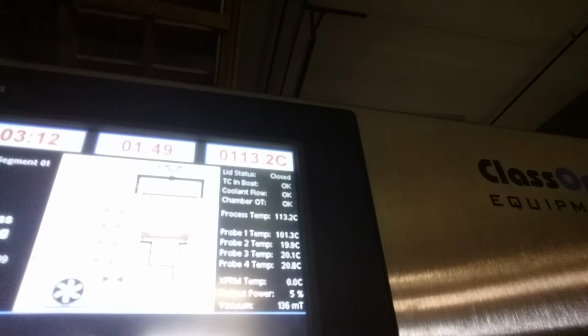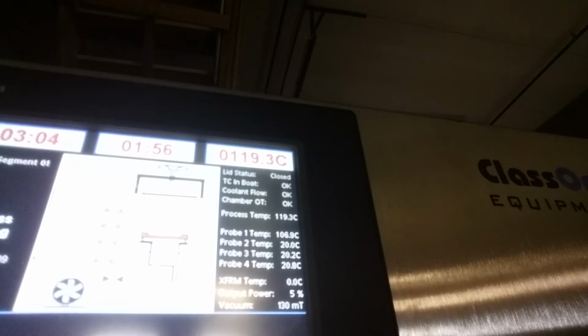So right now we're at 135 millitorr. It's going to keep dropping because we're pumping with the two mechanical pumps. Once we reach 275 degrees, based on this chart that I will email you, the lift is going to go up. We call it a ram here in this diagram here. It pops up and it starts in the up position and then it drops right at 275.